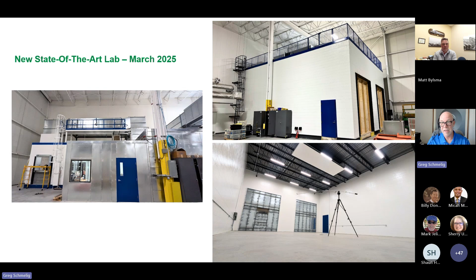When we come to market, we want to see a schedule of silencers that not only has a pressure drop column, as in our laboratory's ideal world, but also a silencer pressure drop with maximum system effect, so you know how to size your equipment to handle pressure drop, whether that means increasing brake horsepower or, in the case of sheaves and belts, ensuring proper sizes and alignments. This is essential to how your systems get laid out and your equipment gets selected.